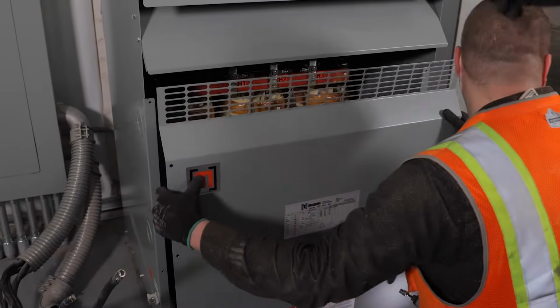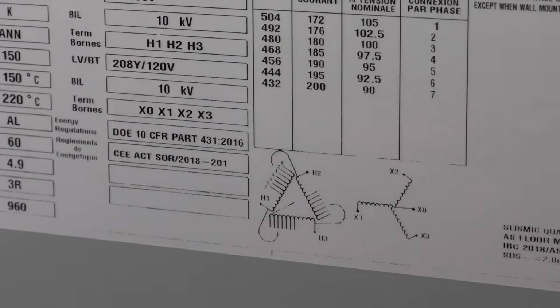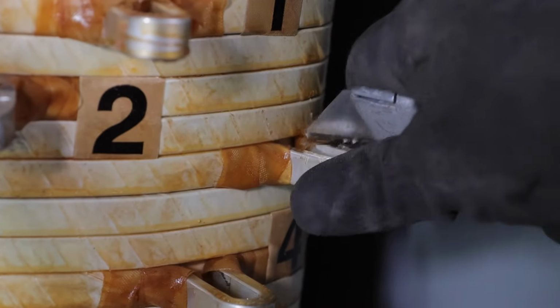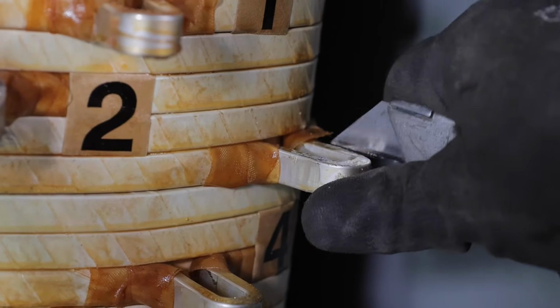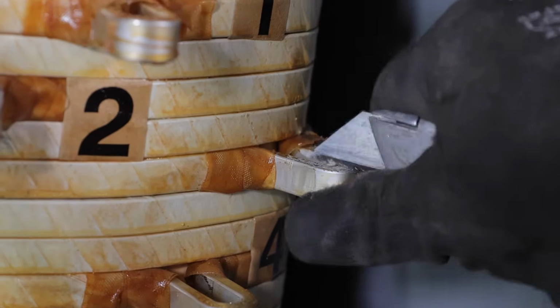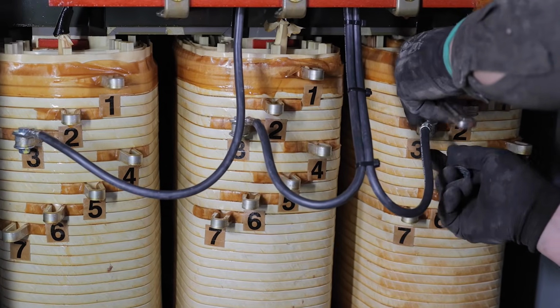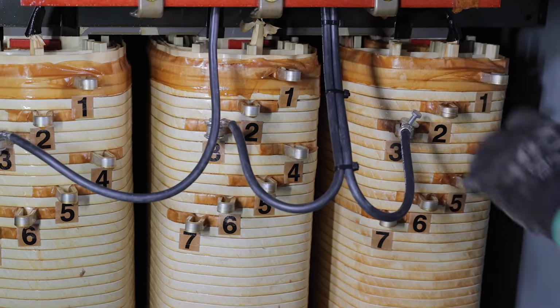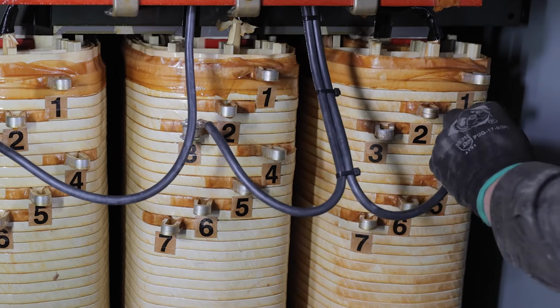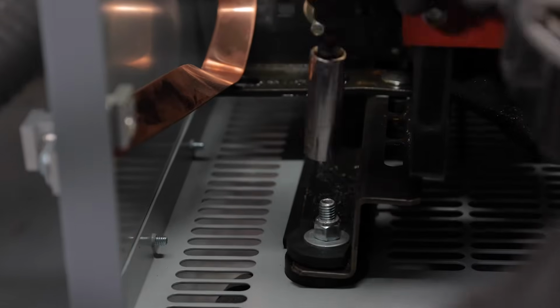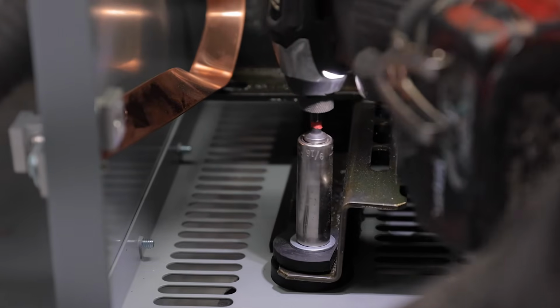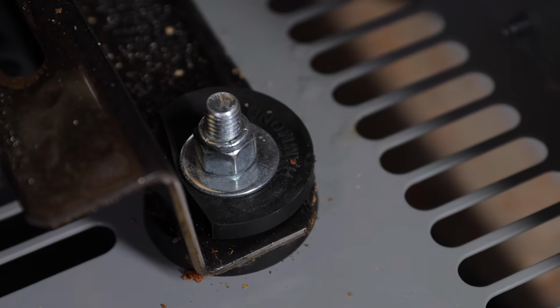If you're adjusting the voltage taps, consult the diagram on the nameplate. The varnish is removed from the top and bottom of the tap terminal with a razor knife or wire brush prior to changing the tap leads for a solid electrical connection, and the tap lead is moved to the appropriate setting on each coil. The internal isolation pads can be loosened slightly to help dampen vibration and keep the noise down.